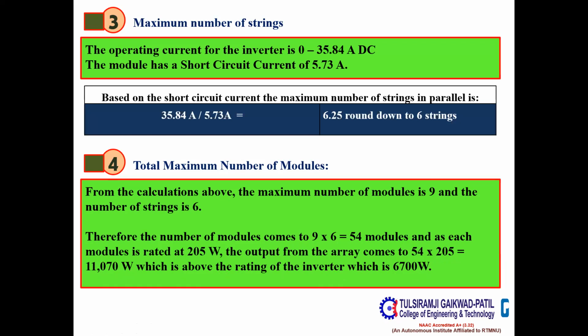and we have also calculated the maximum number of strings which are to be connected in parallel, because we know that in series the voltage would add up and in parallel the current would add up. So if we want to increase the current, we need to arrange the system in parallel. If we need to build up the voltage, we need to connect the system in series. So naturally, series and parallel combinations would be required by us, right? But how many such strings should be there? What should be the optimum number? These are the points which we need to actually calculate, looking towards the site consideration, the requirement of the customer, and the requirement of the system.